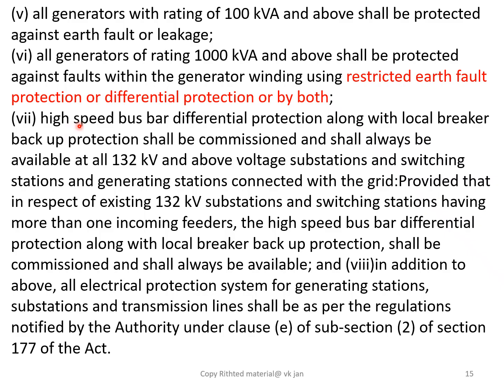Next, high speed bus bar differential protection along with the local breaker backup protection shall be commissioned and shall always be available at 132 kV and above voltage substations and switching stations and generating stations connected with the grid, provided that in respect of existing 132 kV substations and switching stations having more than one incoming feeder, the high-speed busbar differential protection along with the local breaker backup protection shall be commissioned and shall always be available. In addition to the above, all electrical protection equipment for generating stations, substations and transmission lines shall be as per regulation notified by the Authority.